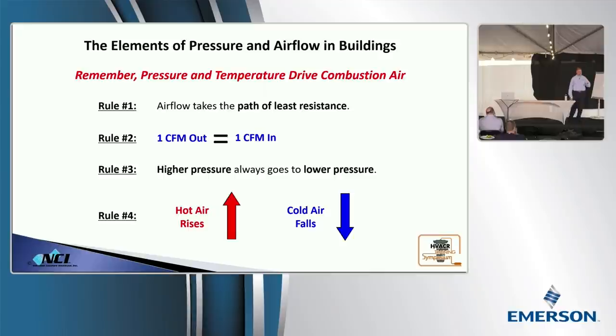I'd recommend you either take a photo of these or write them down. This is your super complicated diagnostics rules to follow. These four rules, guys, most complicated things you run into on combustion air are going to boil back down to these typically. And some guys may switch these up, that's cool. I just want you to remember them and know how they apply to what we're getting ready to talk about. First rule, everybody can say it at once, path of least resistance. We know this stuff. Air always takes the path of least resistance. Air's lazy. We have to direct it.